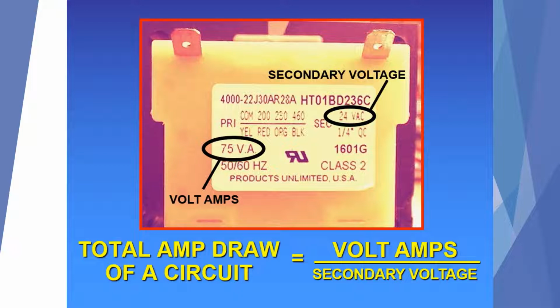By using Ohm's law, which you should have heard of by now, we've actually done a video on it. By using Ohm's law, we can determine how many amps we can apply to this transformer and still be safe to operate. By taking our volt amps, which is the 75 VA rating, and dividing it by our secondary voltage, which is 24 volts AC, we find that this transformer can handle 3 amps of additional load on it to operate successfully.